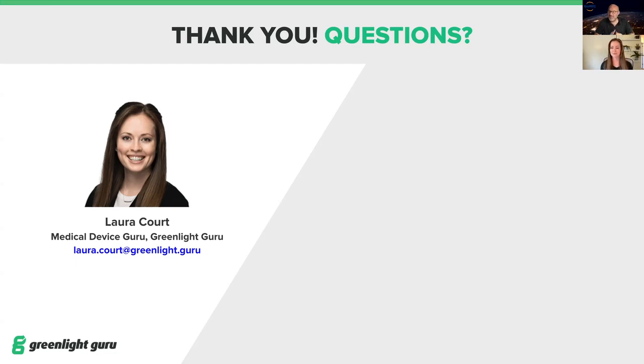Great. When you talk about a validated software, do you provide an information packet to the company to integrate into their quality system? So yes, we do. When it comes to our validation, I always say it's a very fun week around our office when we are getting ready to do a new release that requires new OQs and PQs and involves a lot of us sitting at our computer, taking screenshots, making sure our validations are good. There are, I believe, about 13 different OQs and PQs that we complete that we then provide to you as well, along with written out memos as far as what has been updated that you will put into your system as well.